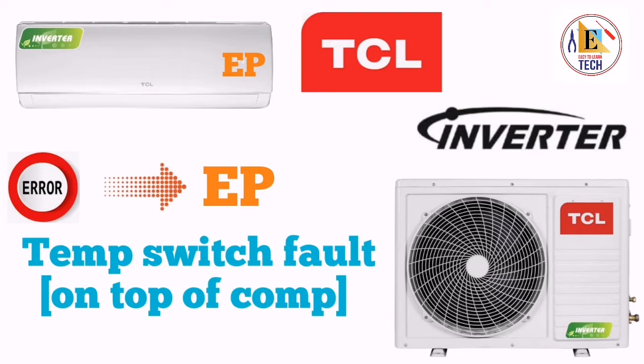And if the compressor temperature is high, or if there is some bad smell, then you have to check your UVW wire of the compressor. The UVW wires should be red, white and blue, and if they are not properly connected, connect them properly. And again you check the unit, and again if you are getting the same problem, then you have to check the pressure of your refrigerant. And if the pressure of your refrigerant is low, you have to add the refrigerant and make it normal.